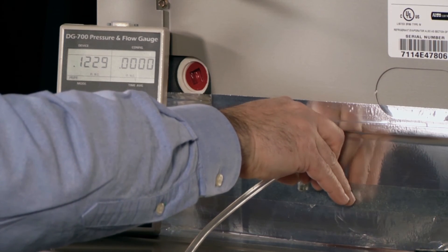So this is important. Don't just use the hose itself. A static pressure probe costs about $15 or $20, and it results in a much more accurate and repeatable measurement. It's well worth the cost, and it's required by our program.